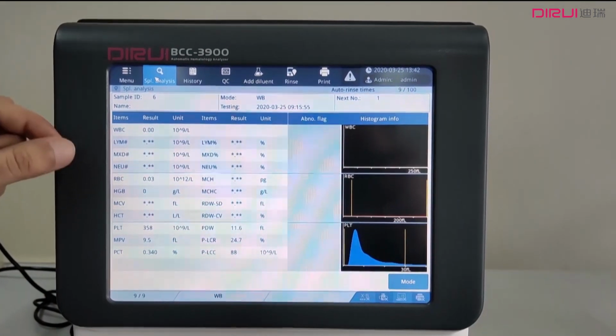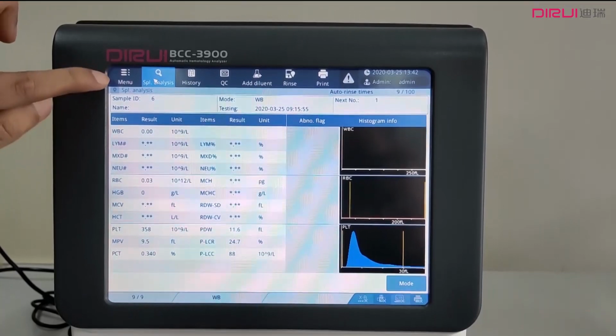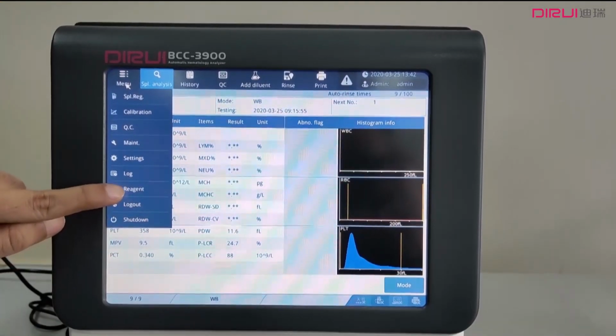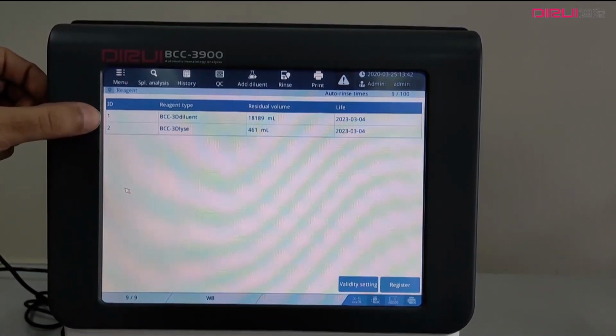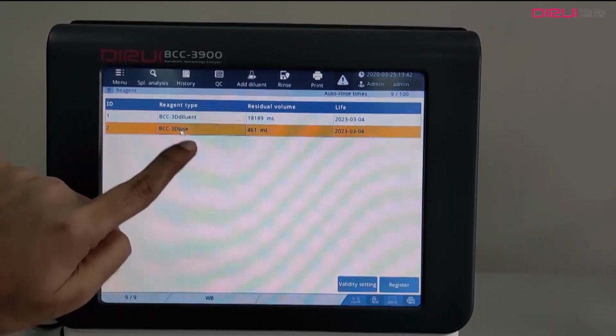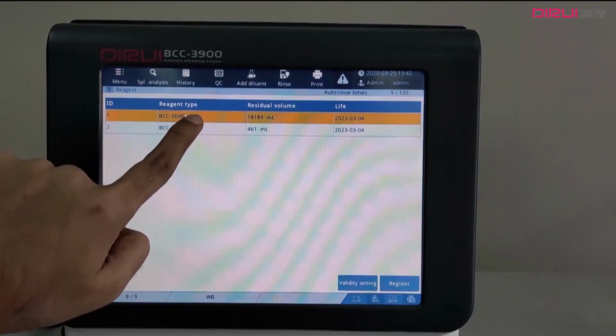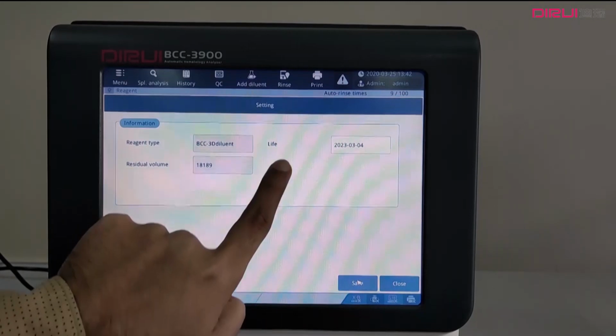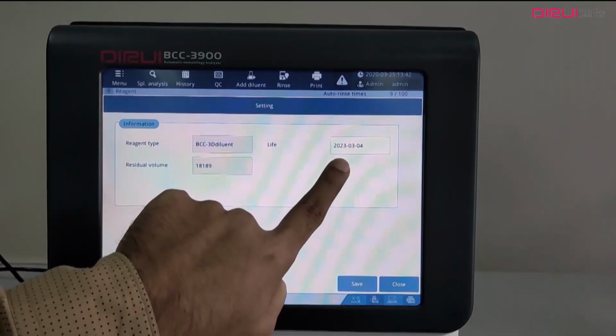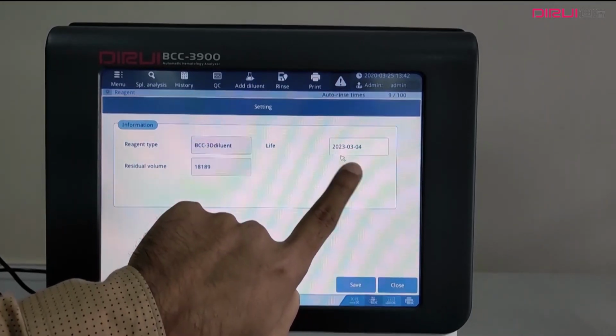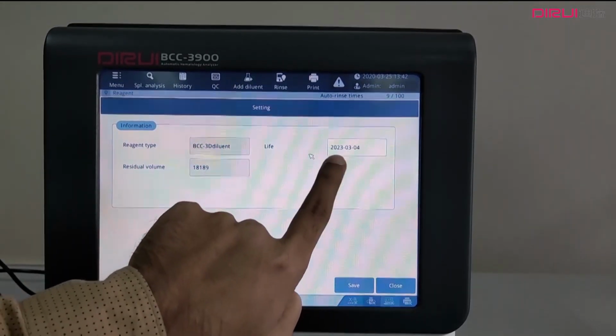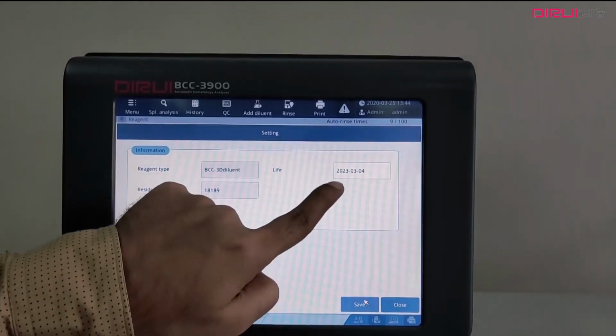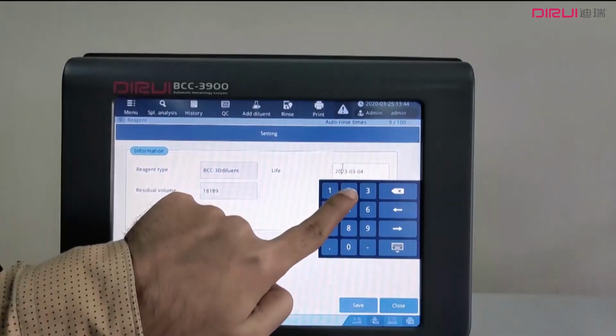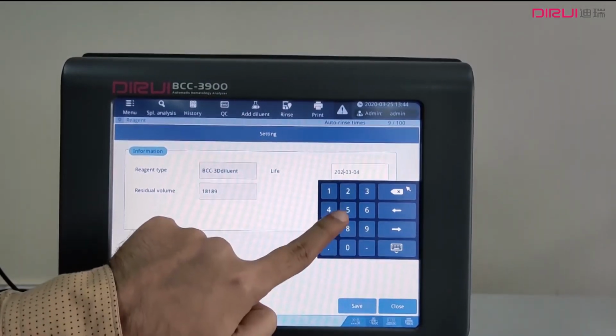Before testing, we need to register our reagents. So for that purpose, you need to go to menu, and there is a reagent tab. So currently, as I told you, this machine is simple and only uses two kinds of reagents. So here diluent and lyse. Here you can see there are two types of buttons. This is validity setting. You need to select any reagent and press validity. So here you can see actually this button is helping you to edit and save the life or expiry date of the reagent. So currently it is 2023 and I am going to change that to 24.